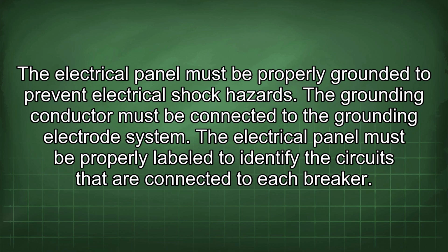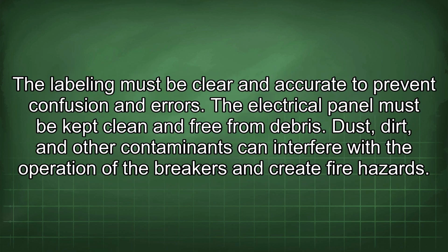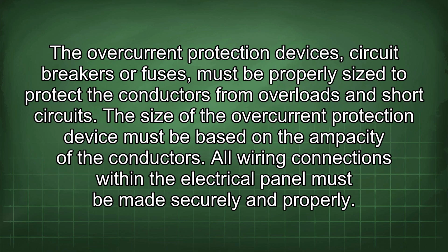The electrical panel must be properly labeled to identify the circuits that are connected to each breaker. The labeling must be clear and accurate to prevent confusion and errors. The electrical panel must be kept clean and free from debris. Dust, dirt, and other contaminants can interfere with the operation of the breakers and create fire hazards. The overcurrent protection devices, circuit breakers or fuses, must be properly sized to protect the conductors from overloads and short circuits. The size of the overcurrent protection device must be based on the ampacity of the conductors.